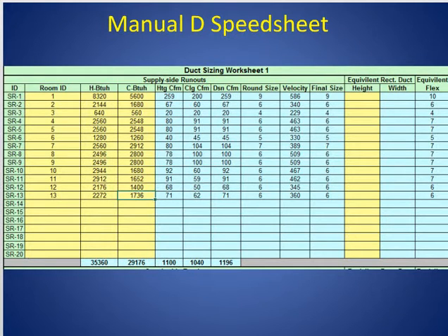It doesn't break it down like in the case of the 4 and 5 diffusers, which there's 2 diffusers in one room there. So we had to divide that room in half, and we're going to give half to each of the 2 diffusers, and that's what we're going to use. And other than that, everything's fairly simple. So if we look in this box here, there's 4 and 5, and we've got 2560. We divided it in half. Each one of them is getting 2560 for heating and 2548 for cooling.